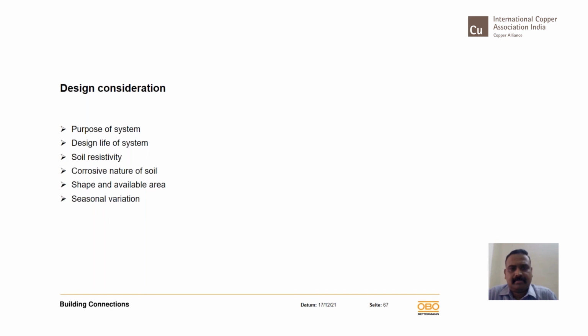One, the purpose of the system is to be understood. The design life of the system needs to be understood. Soil resistivity should be calculated beforehand, not just a theoretical rough value being told, because you will struggle at the last moment in achieving the resistance with the given resistivity. The earthing design depends on the soil resistivity, and based on that the proper designing is done.